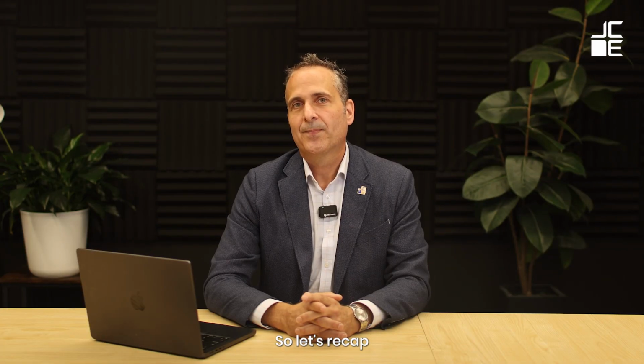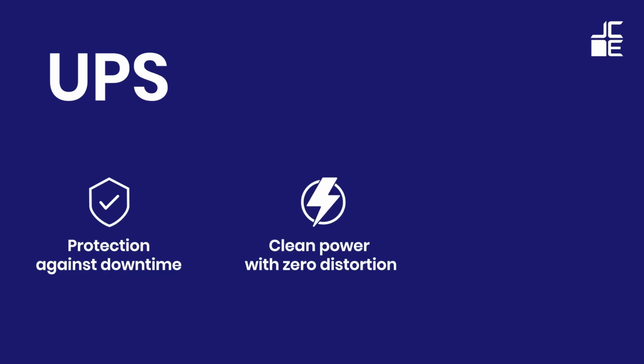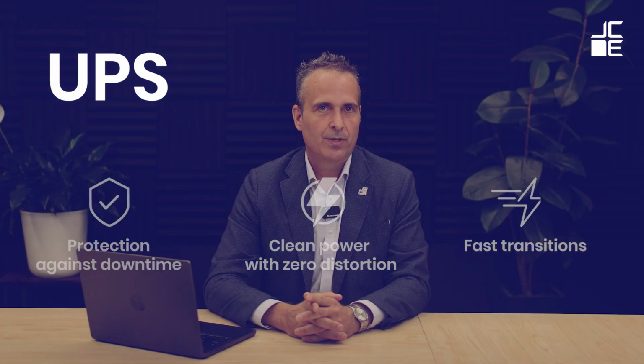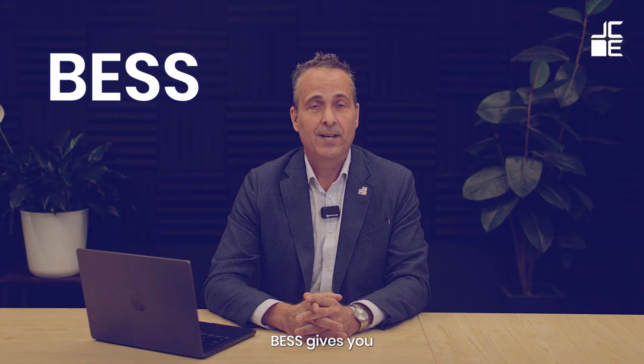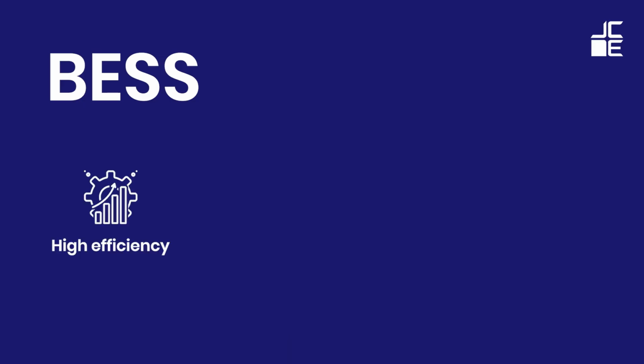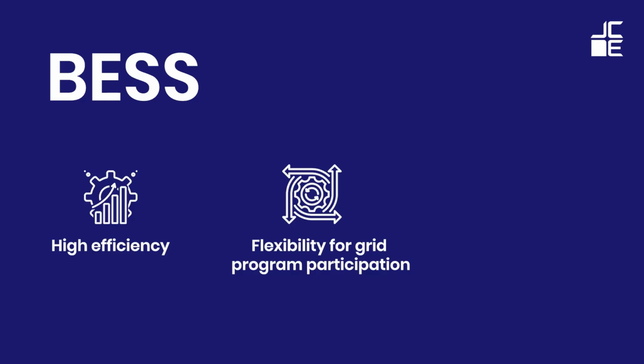So let's recap. UPS gives you ultimate protection against downtime, clean power with zero distortion and fast transitions, perfect for critical loads where even milliseconds matter. BESS gives you high efficiency, flexibility for grid program participation, and strong cost savings by flattening peaks and reducing global adjustment charges. Together, they create an industrial playbook for cost savings, resilience, and sustainability.